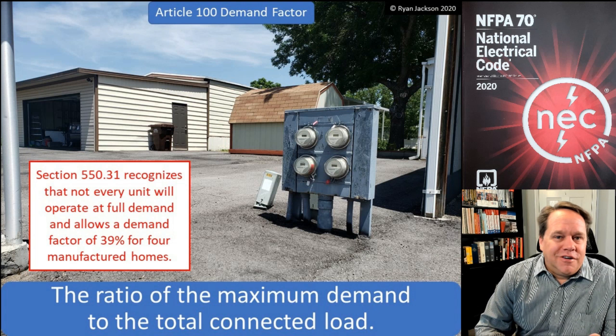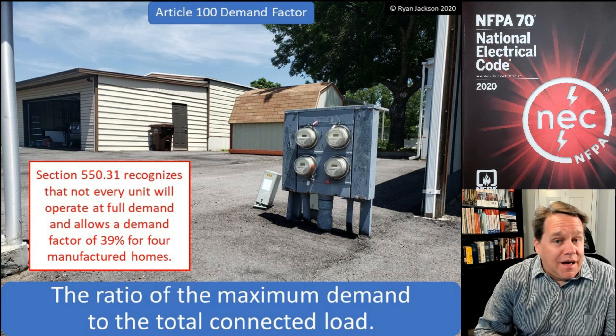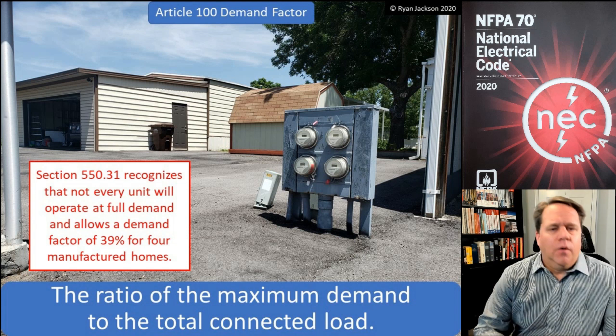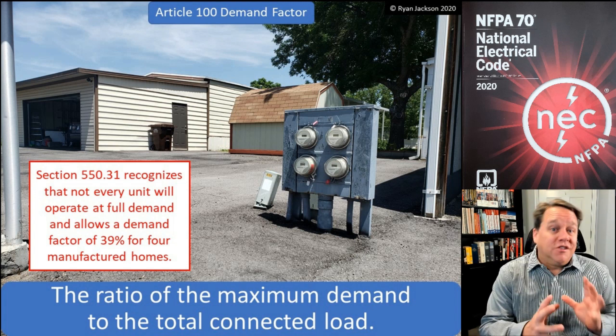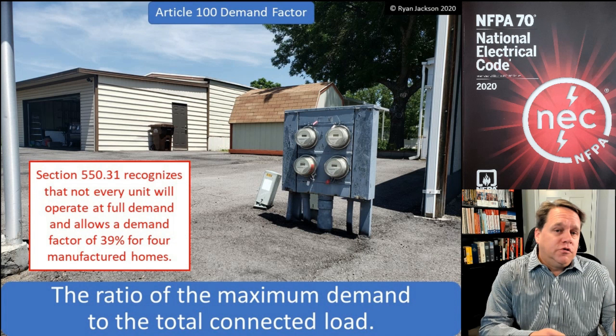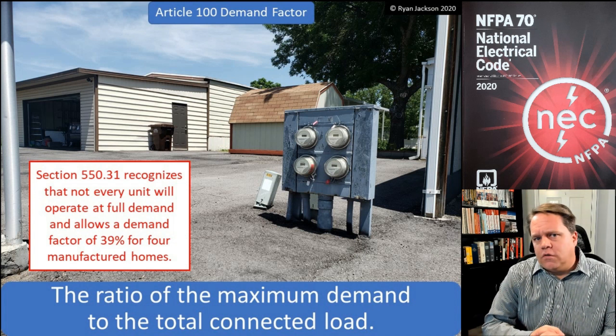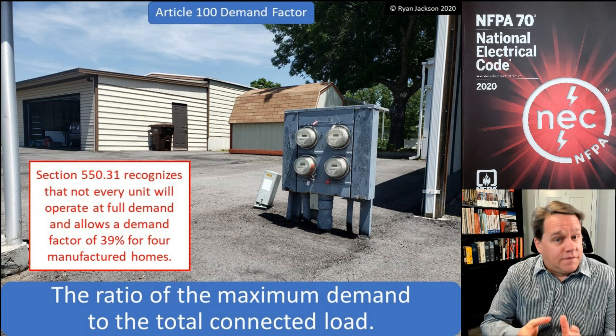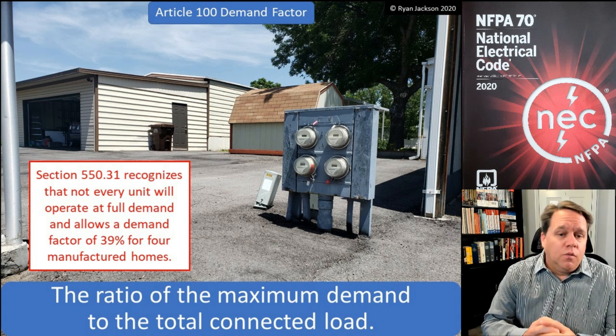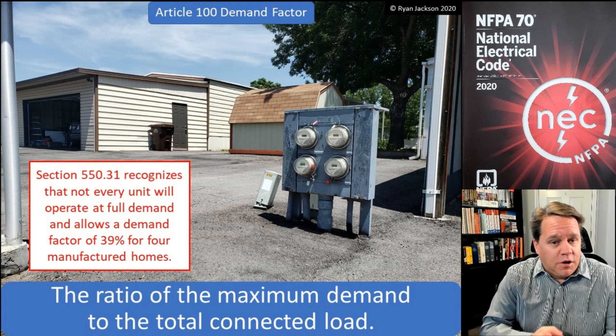Article 100 defines demand factor as the ratio of the maximum demand to the total connected load. Demand factor is something we see a lot in Article 220 for load calculations, and in various other articles as well — for example, Article 550, which covers manufactured homes and mobile homes.